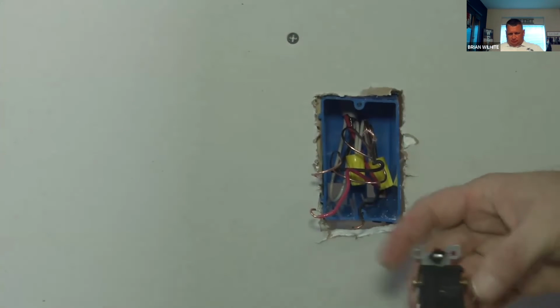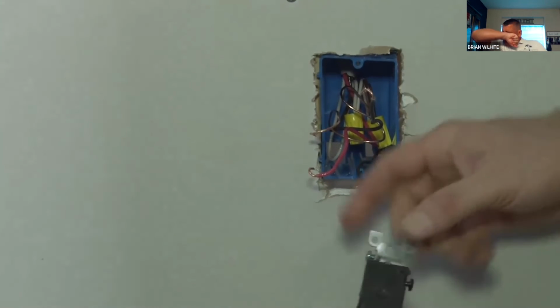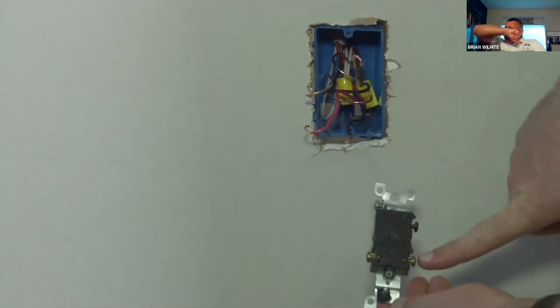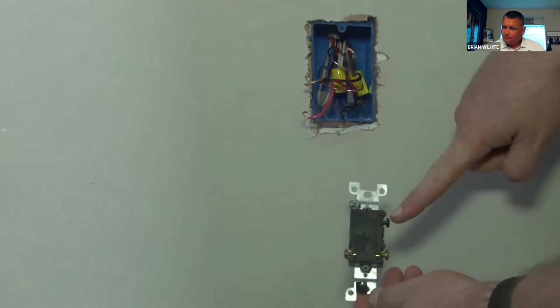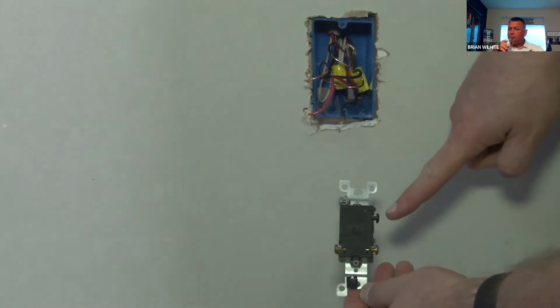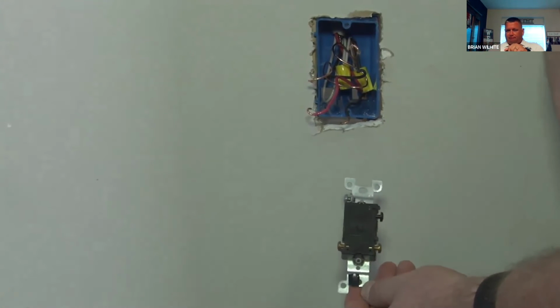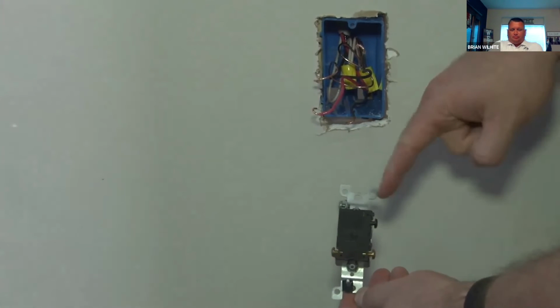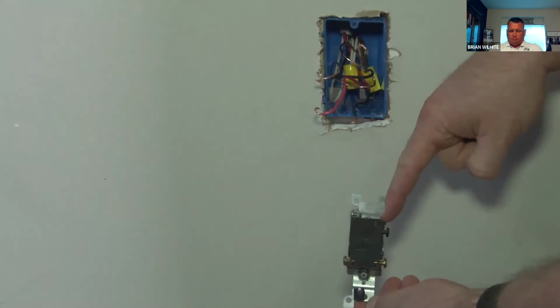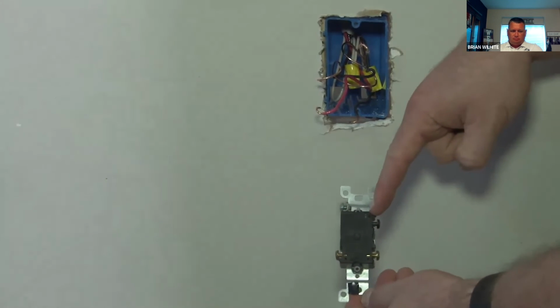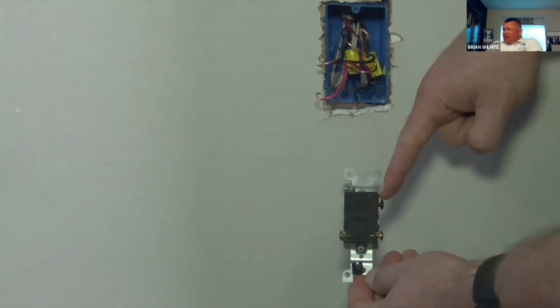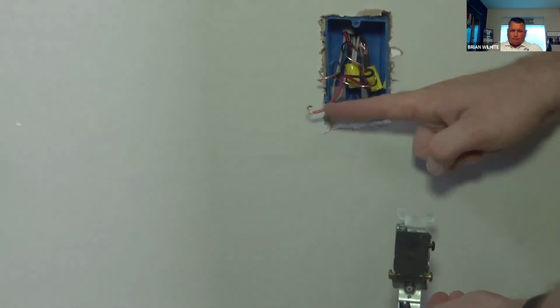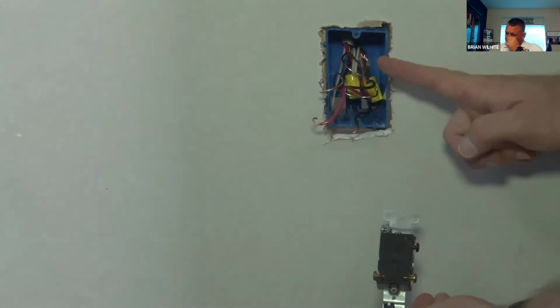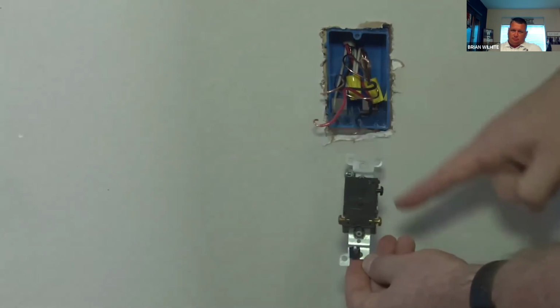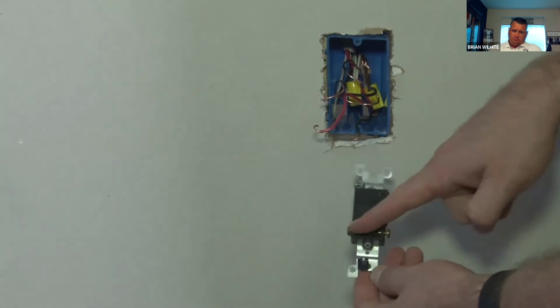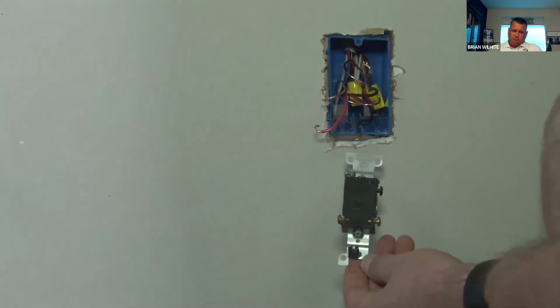On the back of a three-way switch, we have three terminals. Two of those terminals will be regular brass colored. The third terminal is almost black, or it's called antique brass is the color that it is associated with. The one that is almost black, if you're able to see on here in very, very small type, it's identified as the common terminal. Common just means completer of the circuit. These two wires here that I've identified as having continuity are the two wires that connect to the other two terminals. Those terminals are called travelers.